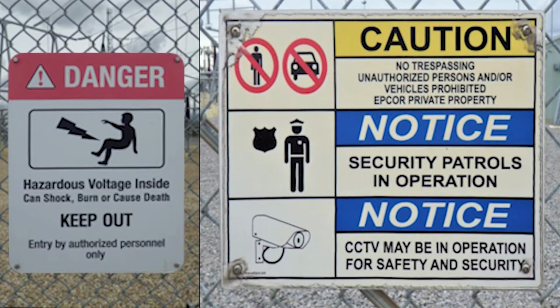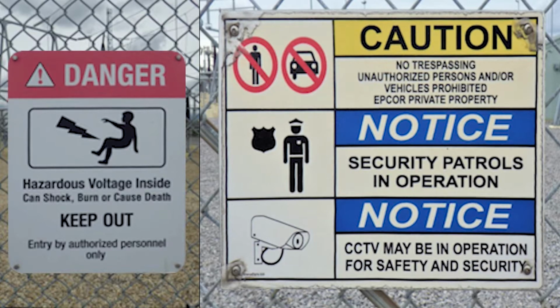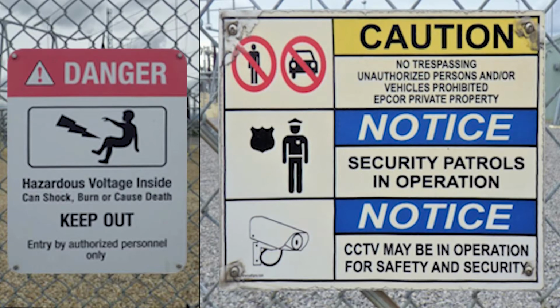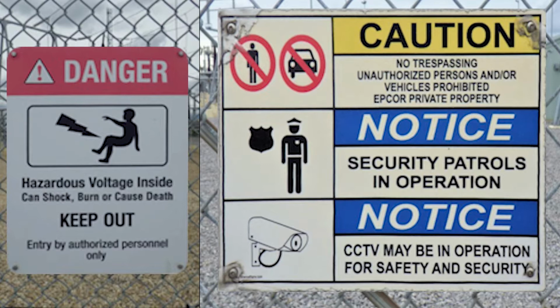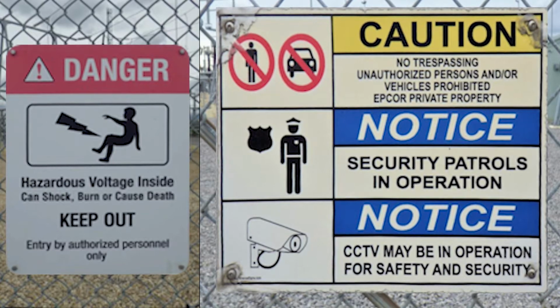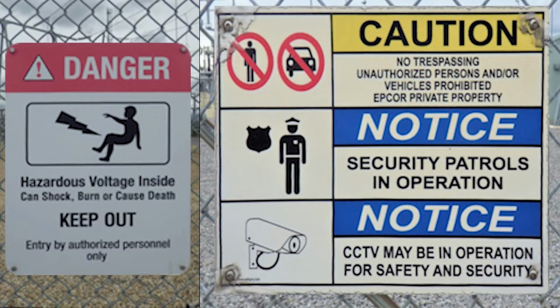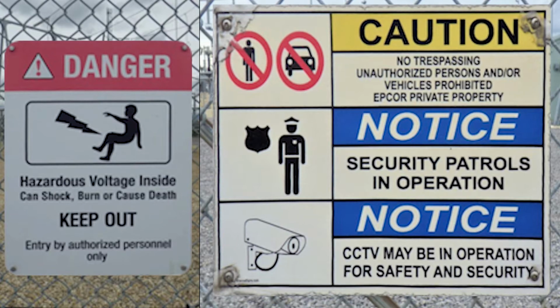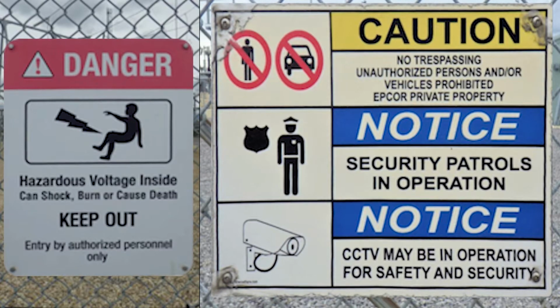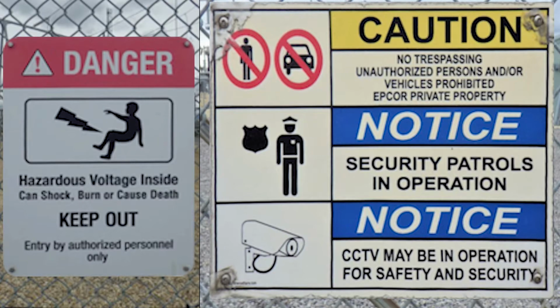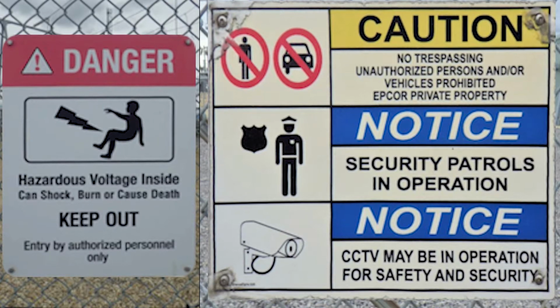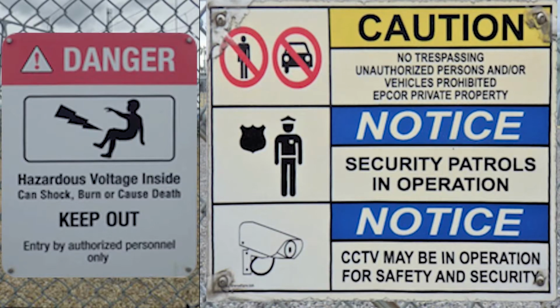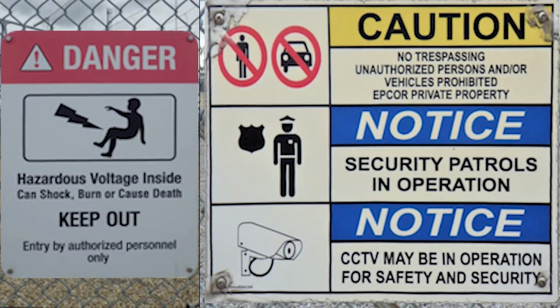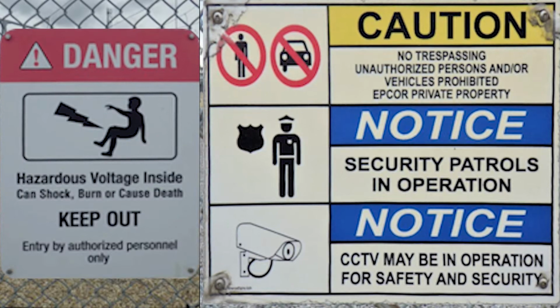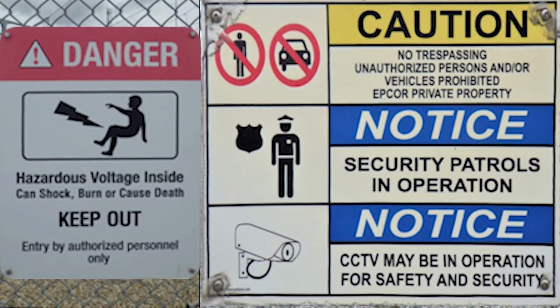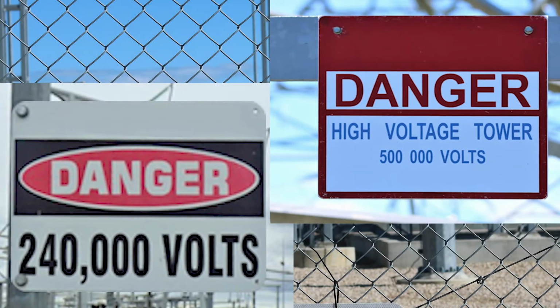We are going to be working in two different substations. The first is a 500,000 volt AC to 250,000 volt AC substation, and the second is a 500,000 volt AC to 500,000 volt DC inverter station. Both of these substations are ultra-high security facilities, and the utility has recently completed repairs on some of their SF6 breakers. They have invited us in to look at their repair work and determine if there's any remaining leaks and to evaluate the camera. Obviously, this is not a typical work environment.